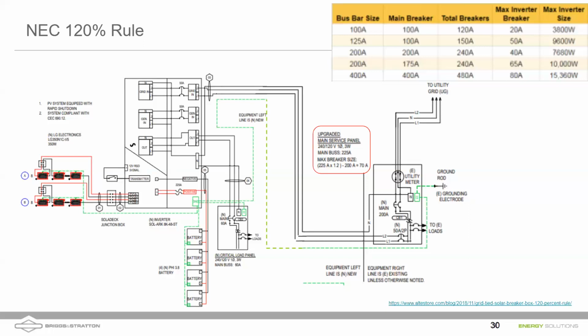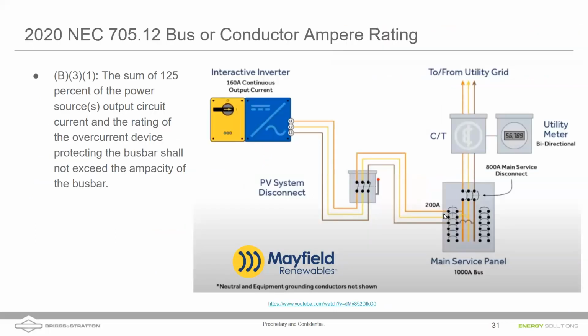The point is, in a worst case scenario, you have all of the loads on in the house, 200 amps coming in from grid, and 50 amps coming in from the backfed solar. We could theoretically exceed the bus bar rating of that main panel, and we could start a fire. We could melt the bus bar. So we're allowed to backfeed a little bit, and there are 3 scenarios that allow us to do this. This is demonstrating the 120% rule.